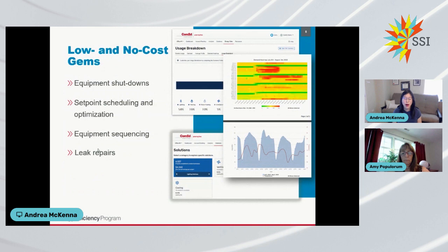One of the most popular ComEd EE programs is the Compressed Air Fix It Now program, where service providers are paid directly to identify and repair leaks at the customer site. So the customer can begin saving energy immediately with no upfront cost. I'd also include maintenance and repairs in this low and no cost category—for example, making sure filter screens are clean and repairing failed sensors.